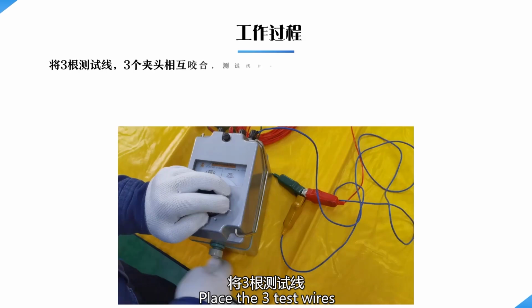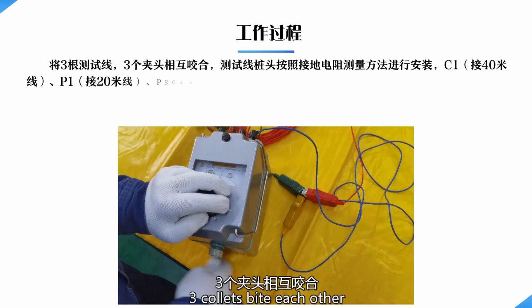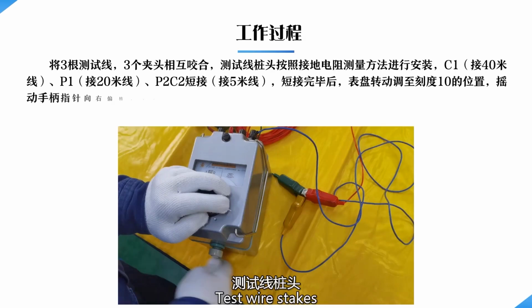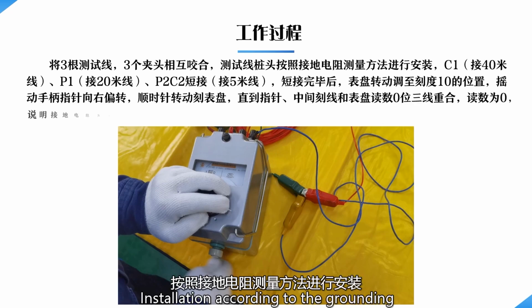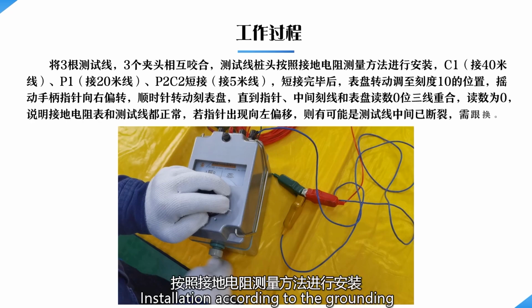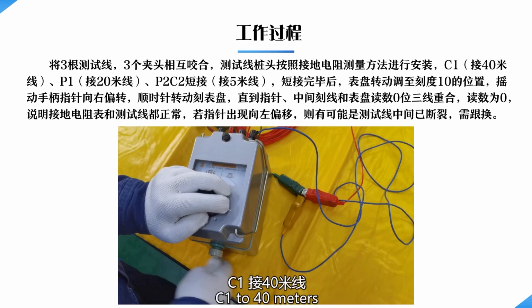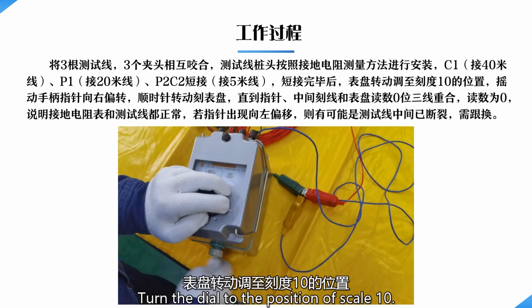Place the 3 test wires. The 3 collets bite each other. Test wire stakes are installed according to the grounding resistance measurement method. C1 to 40 meters. P1 to 20 meter wire. P2 and C2 shorted to 5 meters. After the short connection, turn the dial to the position of scale 10.